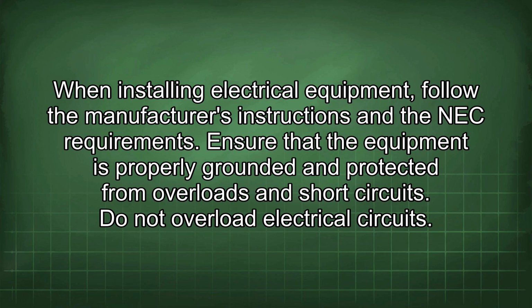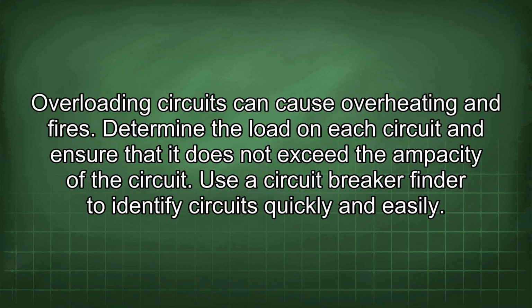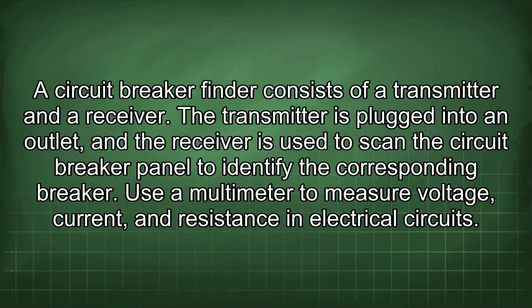Do not overload electrical circuits. Overloading circuits can cause overheating and fires. Determine the load on each circuit and ensure that it does not exceed the ampacity of the circuit. Use a circuit breaker finder to identify circuits quickly and easily. A circuit breaker finder consists of a transmitter and a receiver. The transmitter is plugged into an outlet, and the receiver is used to scan the circuit breaker panel to identify the corresponding breaker.